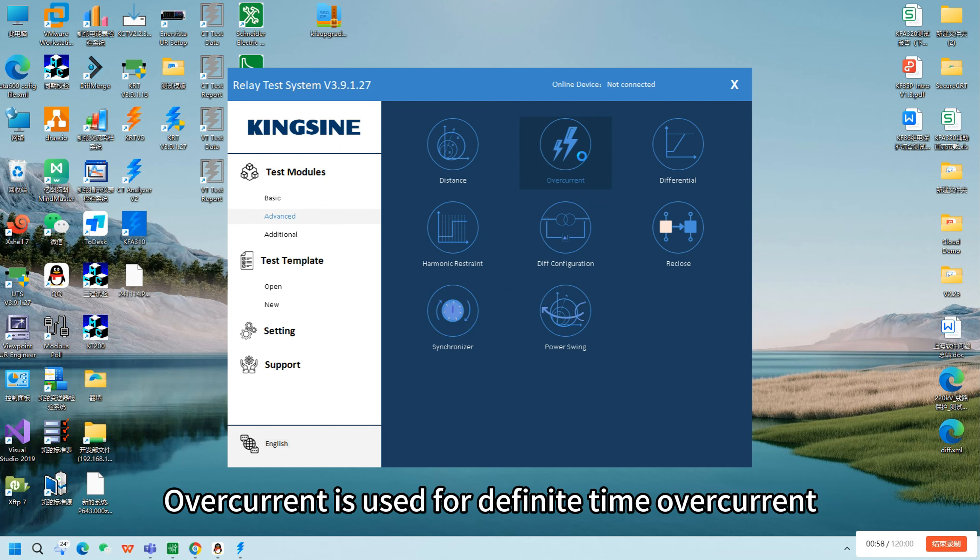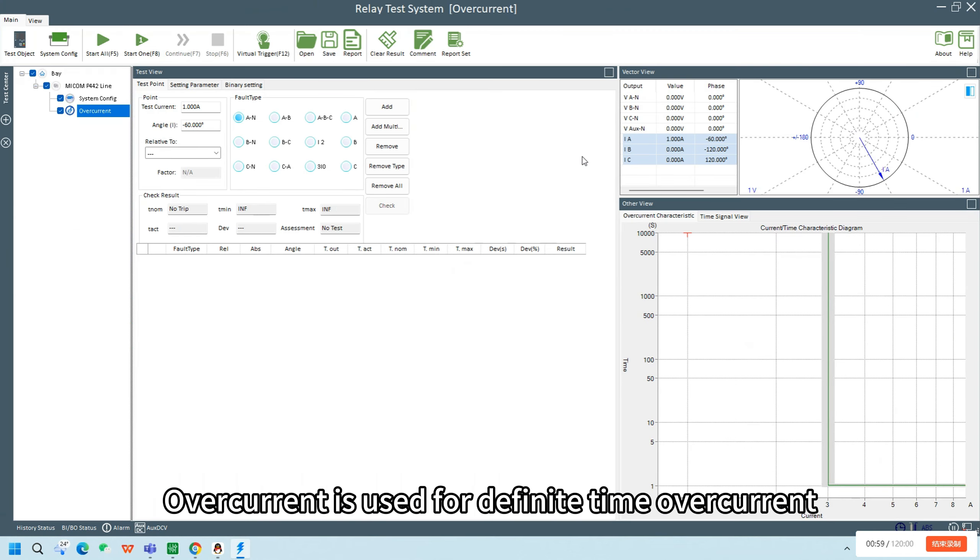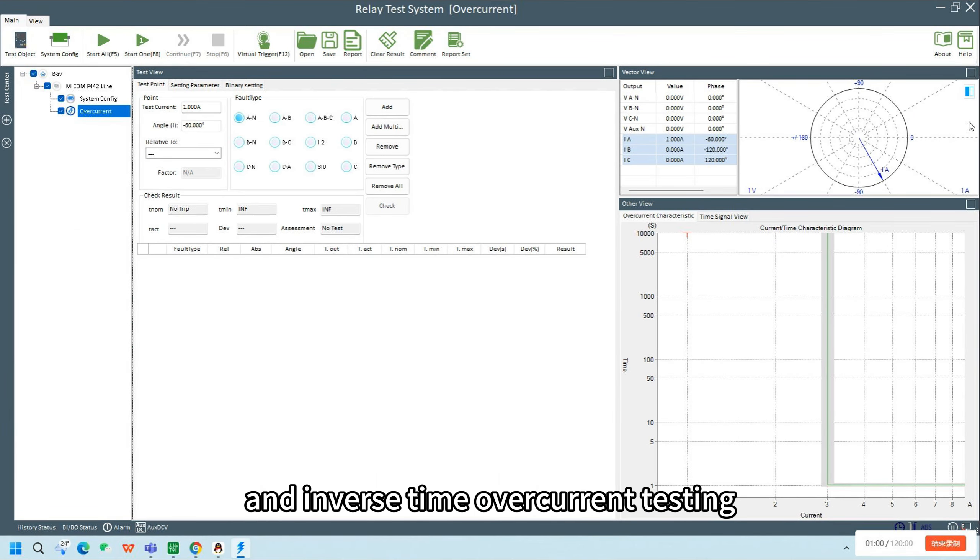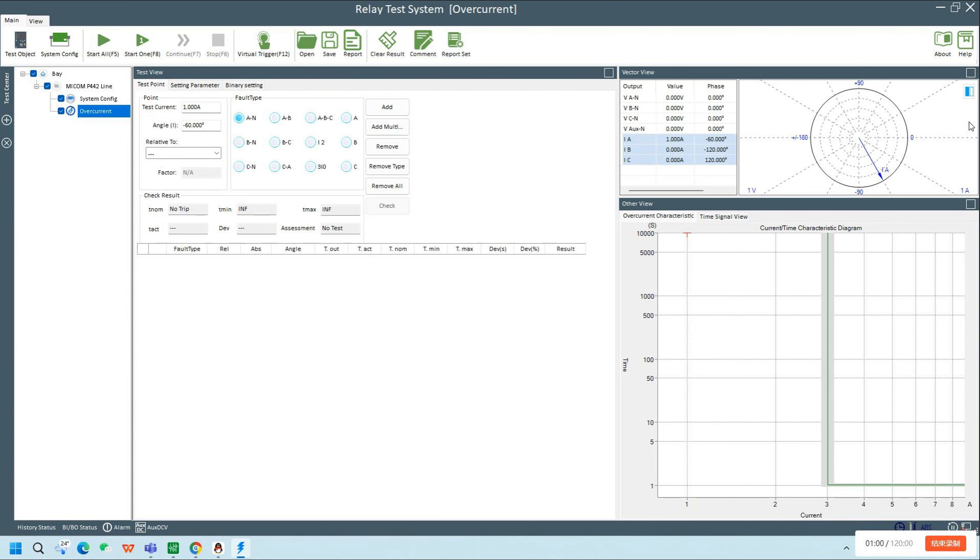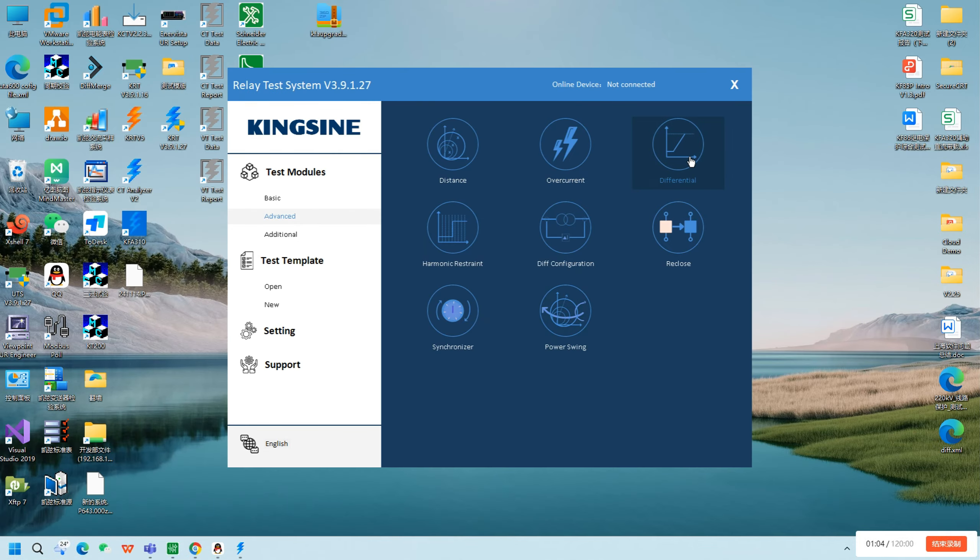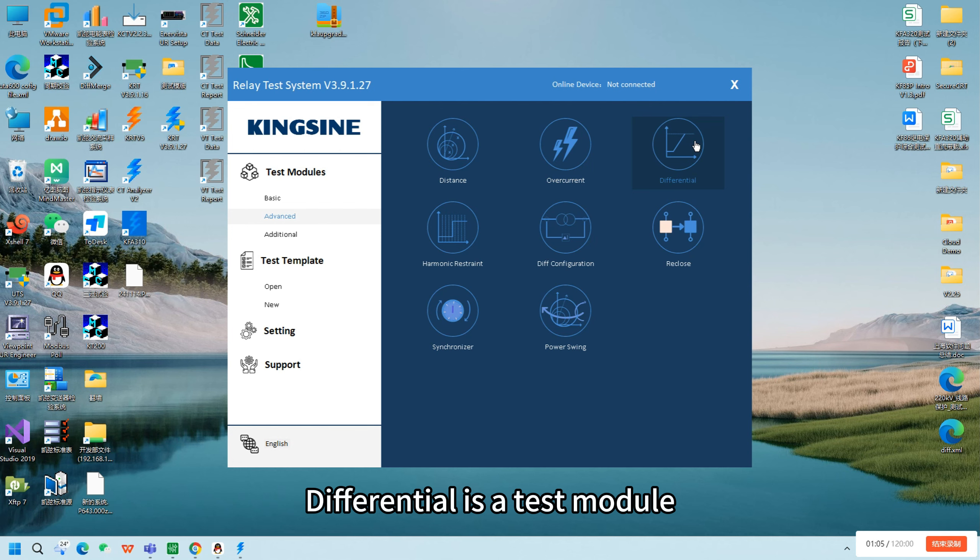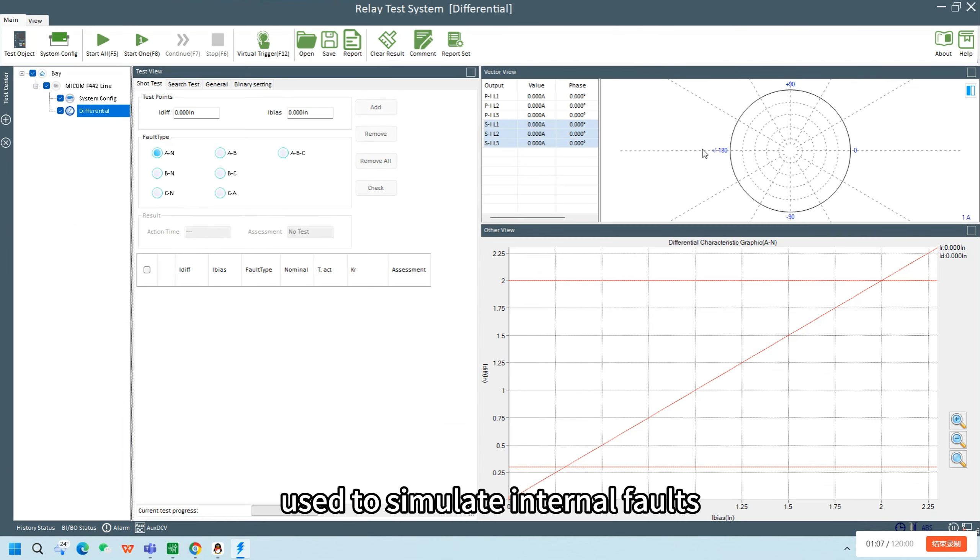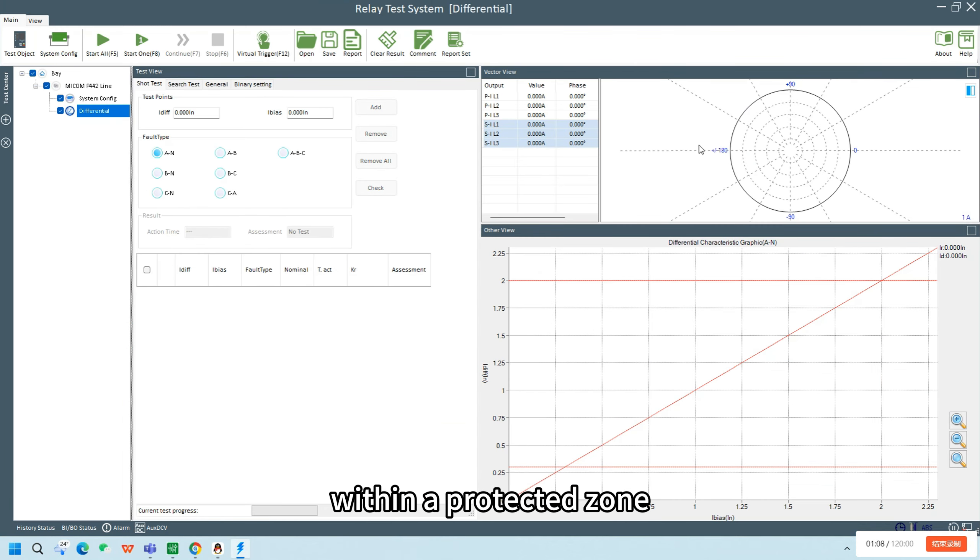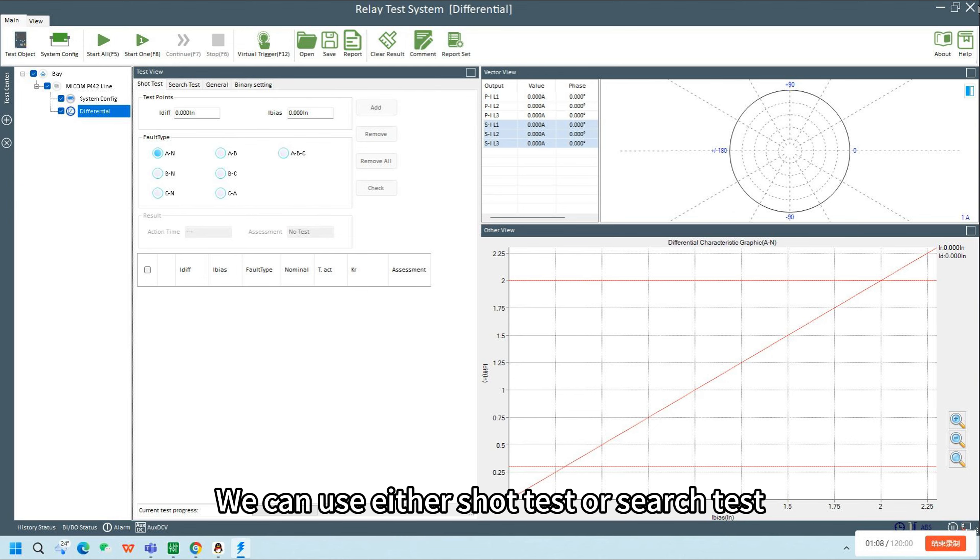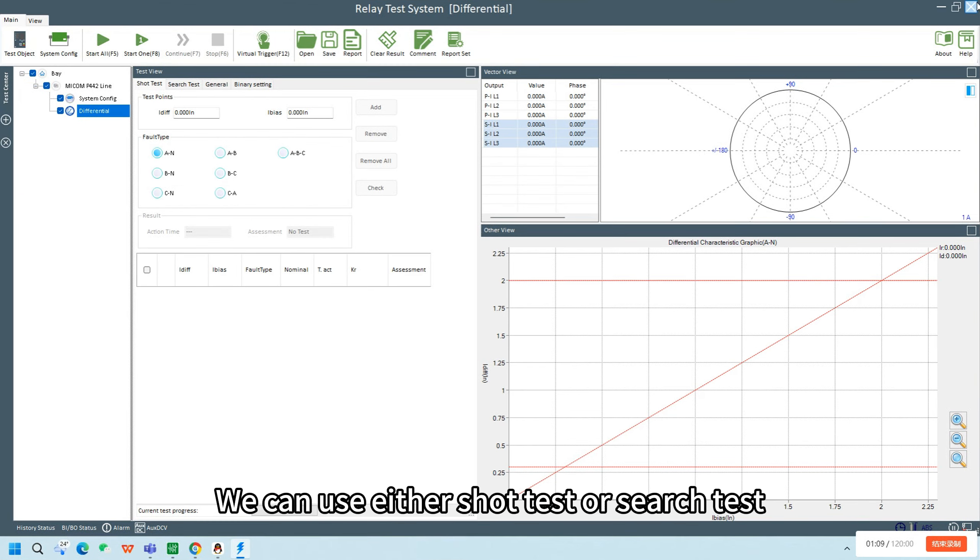Overcurrent is used for definite time overcurrent and inverse time overcurrent testing. We can set various overcurrent curves for testing. Differential is a test module used to simulate internal faults within a protected zone. We can use either shot test or search test.